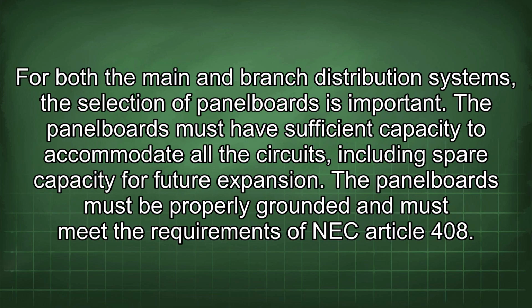For both the main and branch distribution systems, the selection of panel boards is important. The panel boards must have sufficient capacity to accommodate all the circuits, including spare capacity for future expansion.